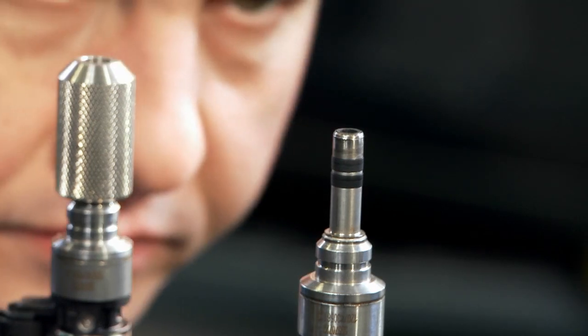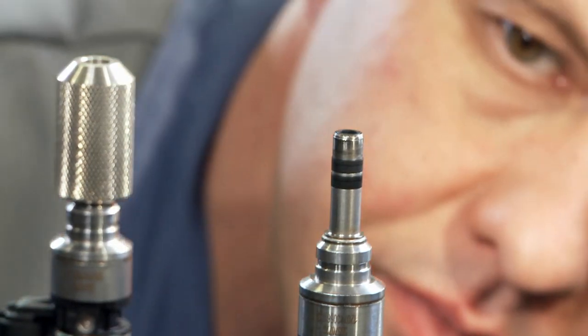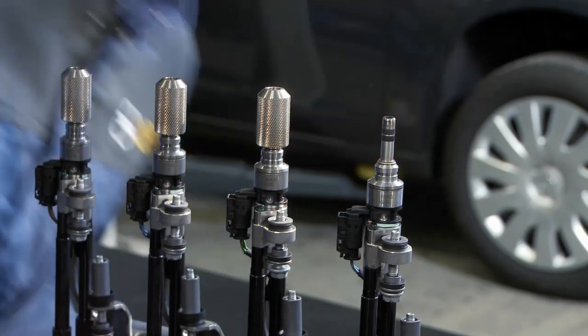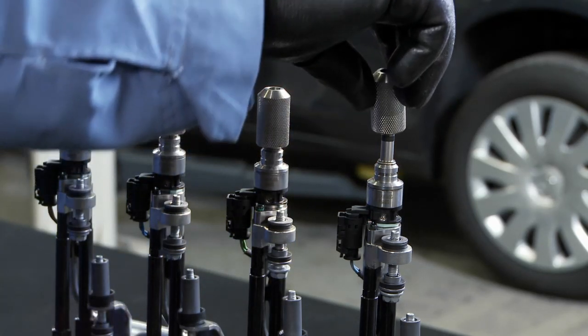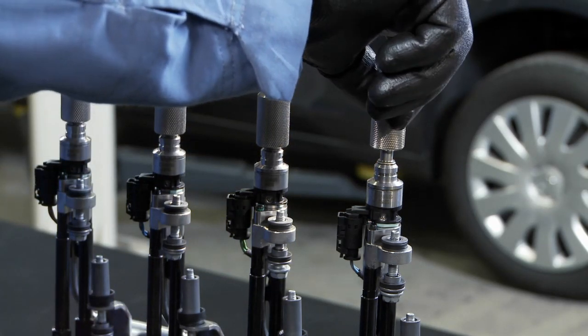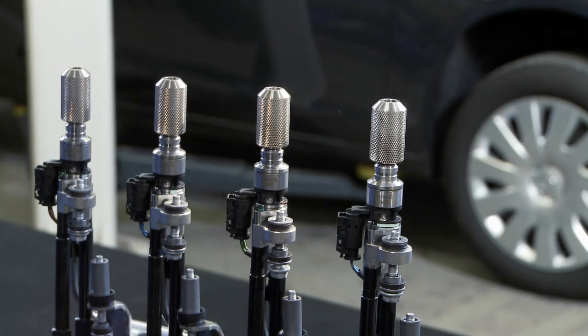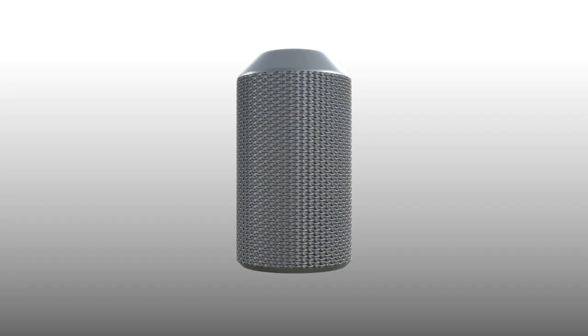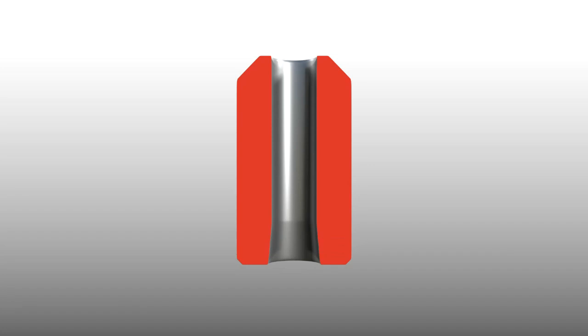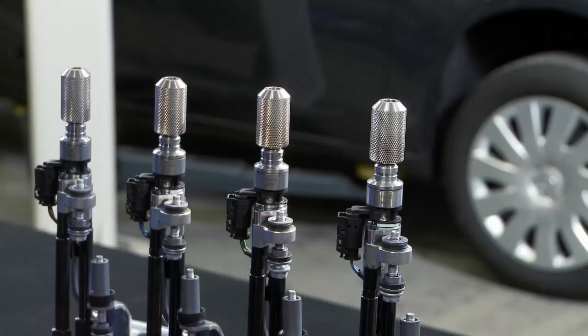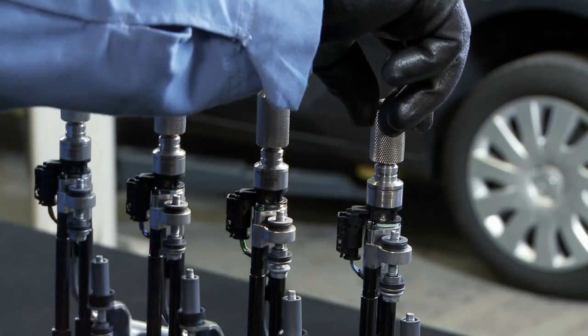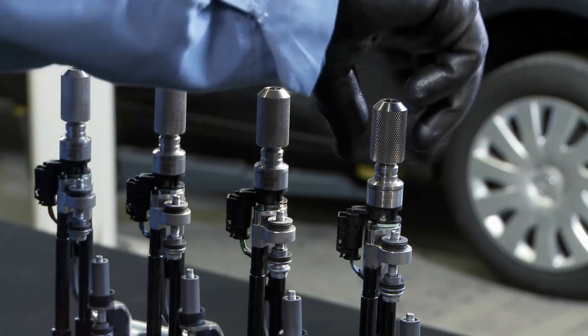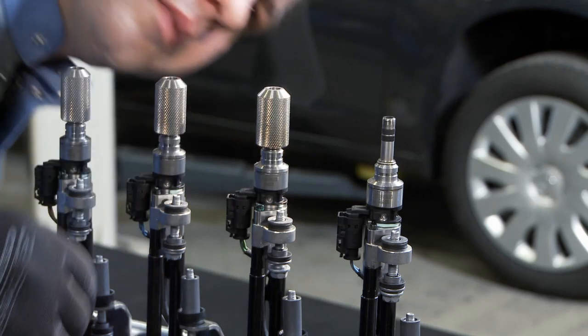Check that the 2 combustion fuel injector seals are correctly seated, and fit the calibration tool by twisting to press the seals further in. The calibration tool is slightly tapered on the inside for this purpose. Remove the calibration tool again to check that the two seals are correctly seated.